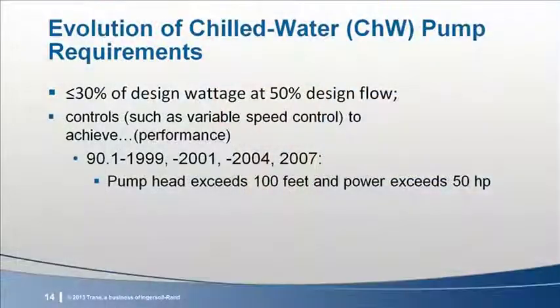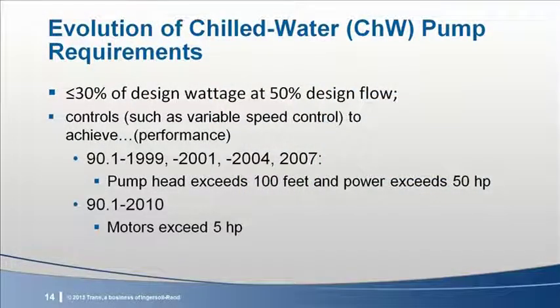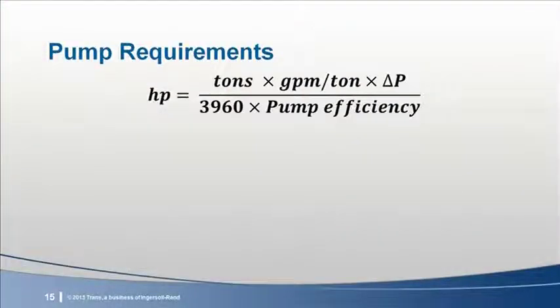So it only applied to large pumps. In the 2010 version, this changed, with a threshold dropping to pumps exceeding 5 horsepower. So, from a practical standpoint, when was VFD-like pump performance required? Using the pump power equation shown here, we can back solve for capacity.